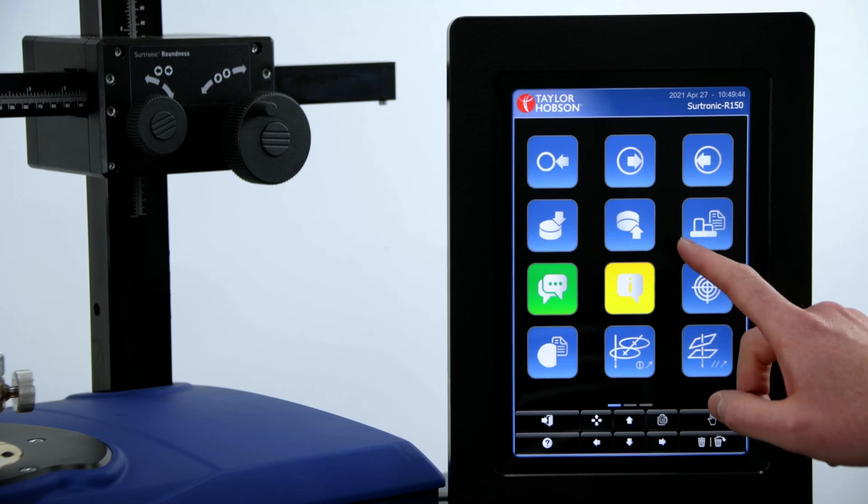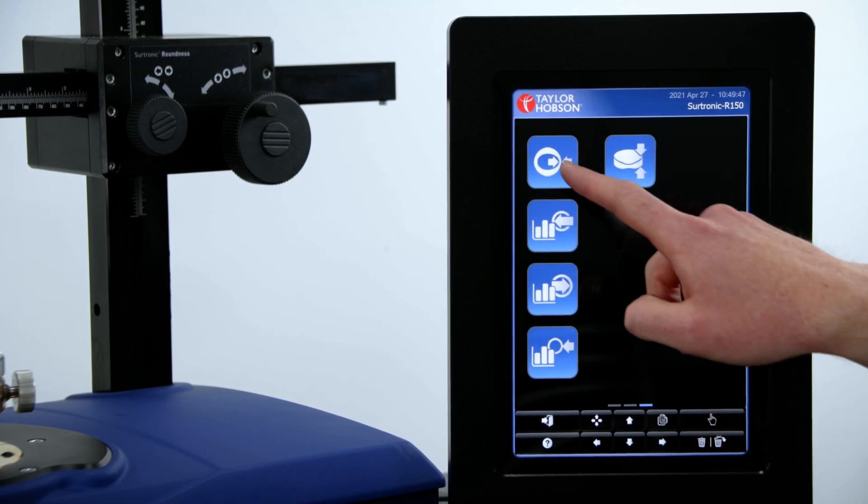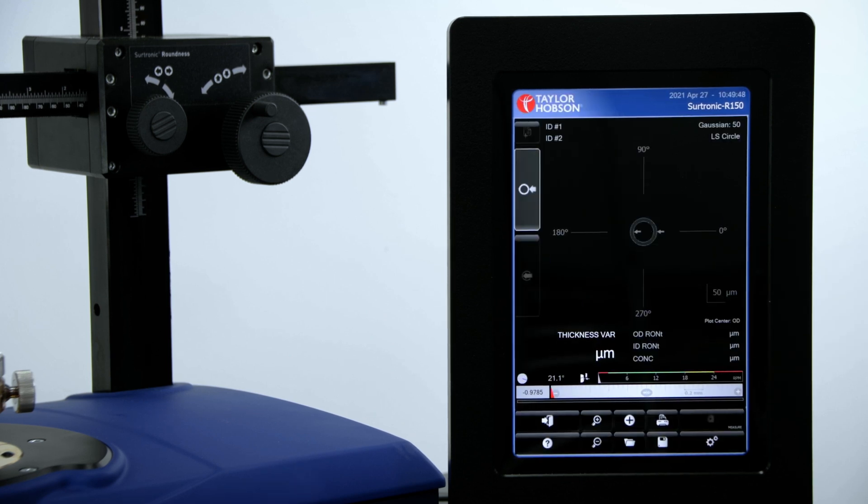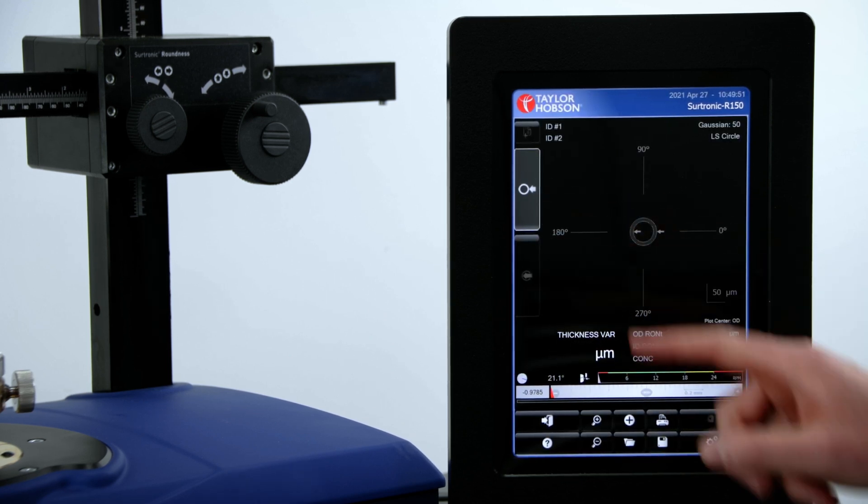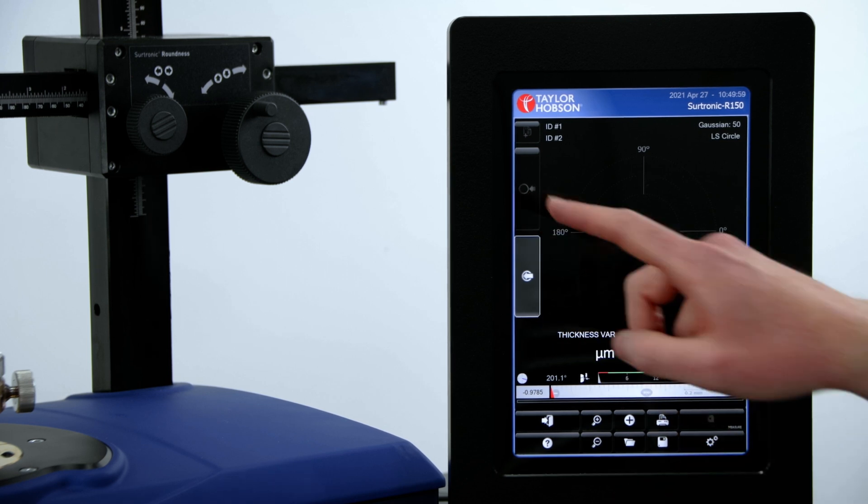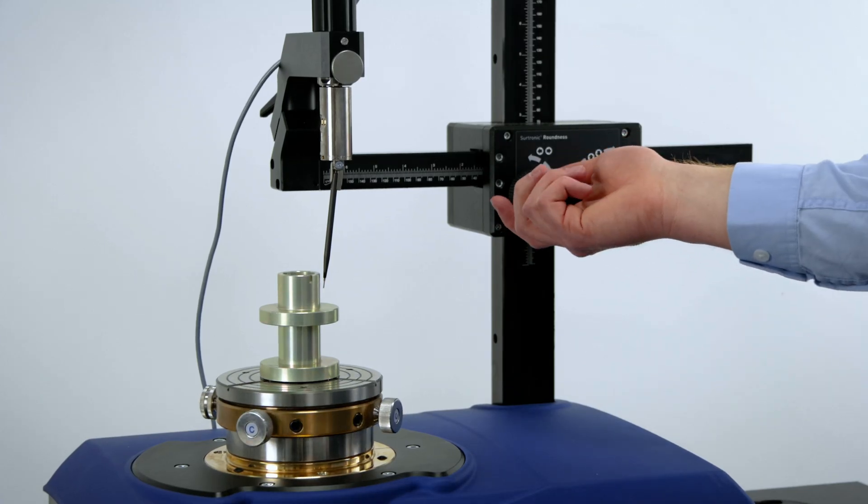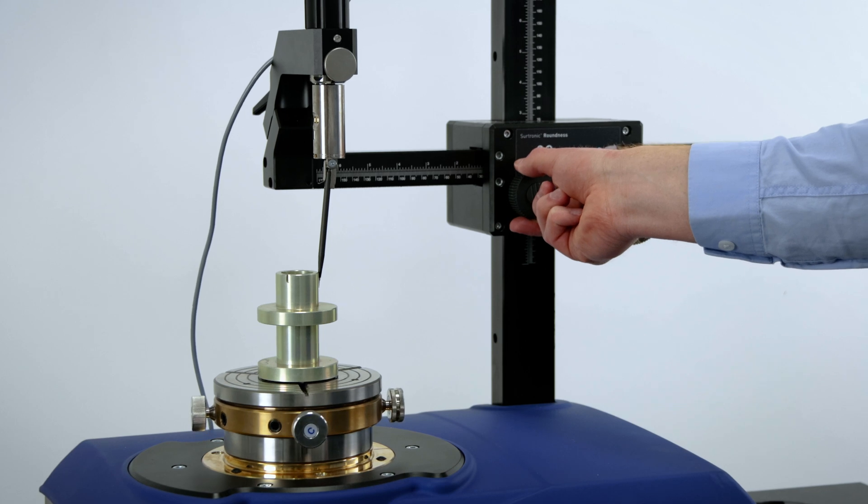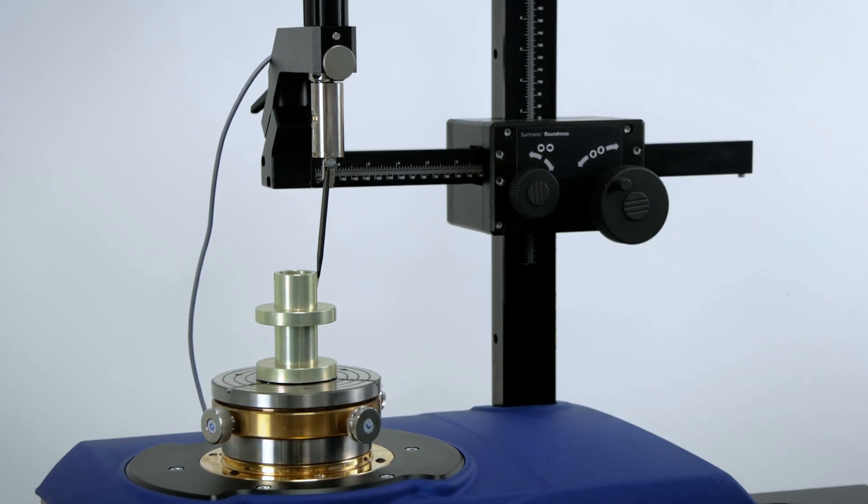To take the measurement, we navigate to the wall thickness app. Once in the app, we have two icons: the first for the outside measurement and the second for the inside measurement. I'm going to start with the outside measurement. For the first measurement, we contact onto the outside of the part and click measure.